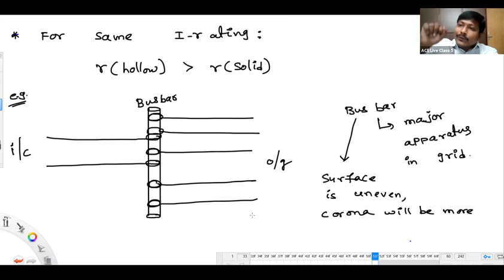Now tell me, among these two conductors, which is suggestible? Is it solid or hollow? Hollow conductor will be suggestible. Why? Because it has more radius, so the electric field intensity on the hollow conductor surface will be less compared to the solid conductor. That's why most of the time for the bus bar, hollow conductor is suggestible, to reduce the corona loss. So for bus bar, hollow conductor is used to reduce corona.